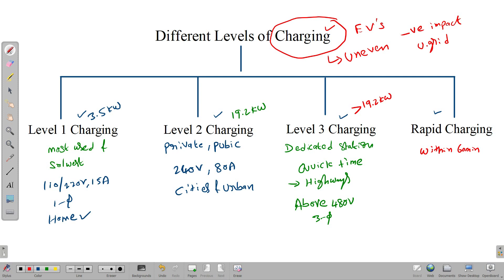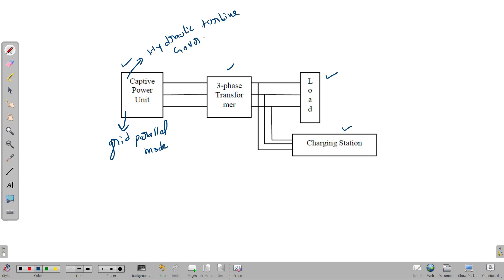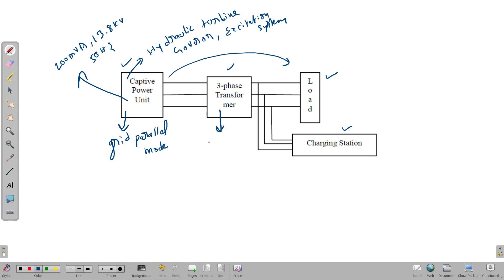Now let's see how electrical vehicle charging stations can impact the power quality of the grid. This is the block diagram of our model. The generation station is a captive power plant connected to the load and charging station through a three-phase transformer. This plant may operate in grid-parallel mode, exporting surplus power to the local electrical distribution network, or in island mode independently. The plant consists of a hydraulic turbine and governor with excitation system. Generator ratings are 200 MVA, 13.8 kV, 50 Hz. The three-phase transformer rating is 200 MVA, 13.8/230 kV, delta-wye configuration.